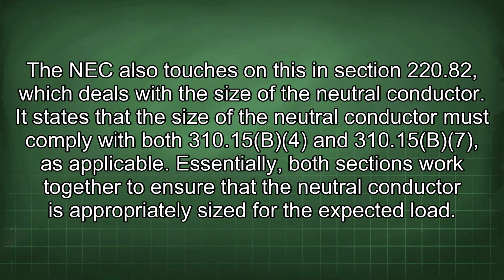The NEC also touches on this in Section 220.82, which deals with the size of the neutral conductor. It states that the size of the neutral conductor must comply with both 310.15(B)(4) and 310.15(B)(7) as applicable.